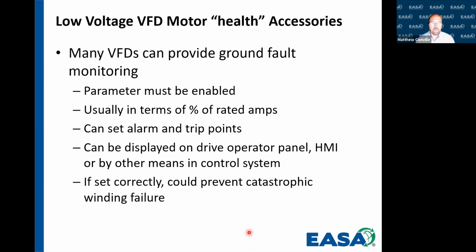When we think about variable frequency drives, one of the most common things that we see are ground faults. So a lot of drive systems now have ground fault monitoring. It's a parameter that has to be enabled. So a lot of times it's not turned on, or if it is turned on, it's at a default value that we may or may not want. It's usually set up in terms of percentage of rated amps of the machine, or in terms of percentage of rated amps of the power section. So it's really important that whenever we're setting it up, we take a look at it. We can set our own alarm and trip points as a result of that percentage rating.